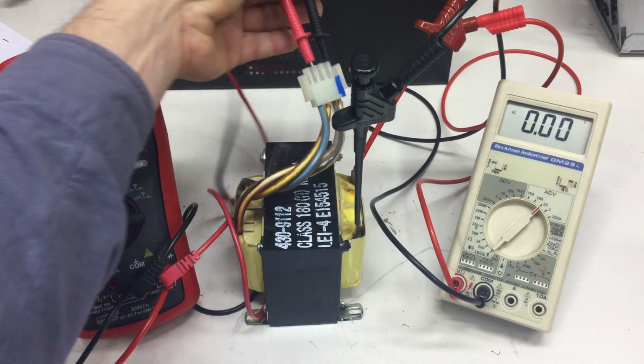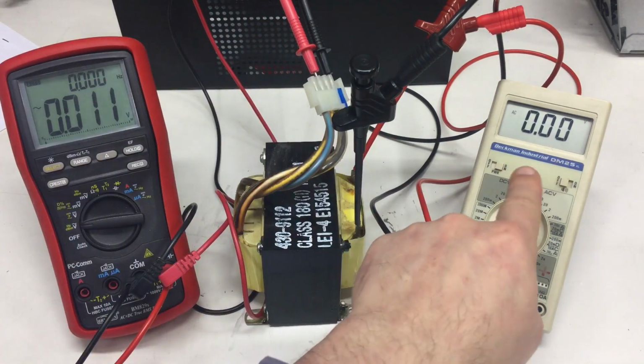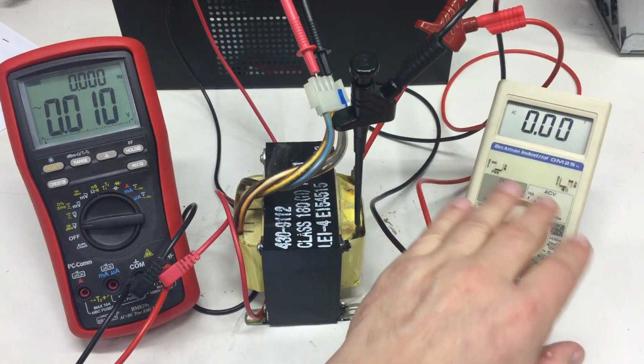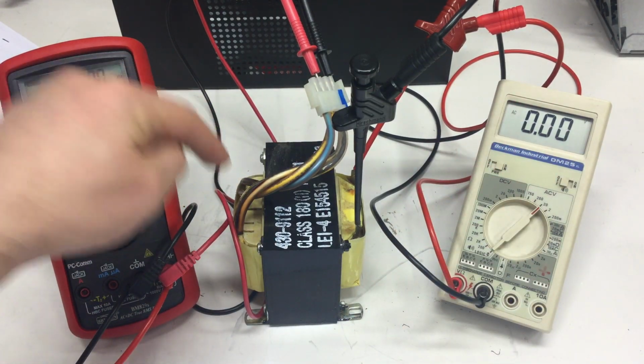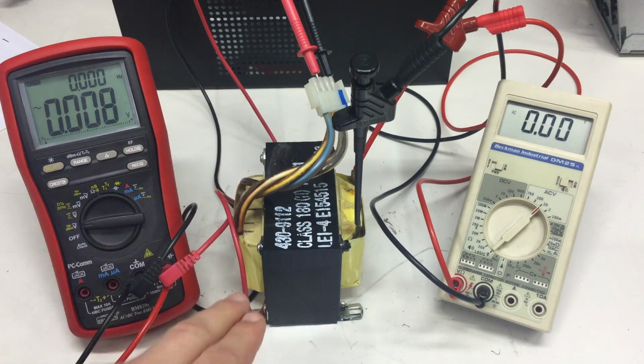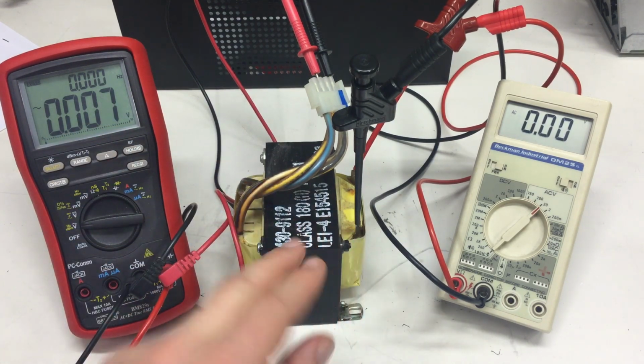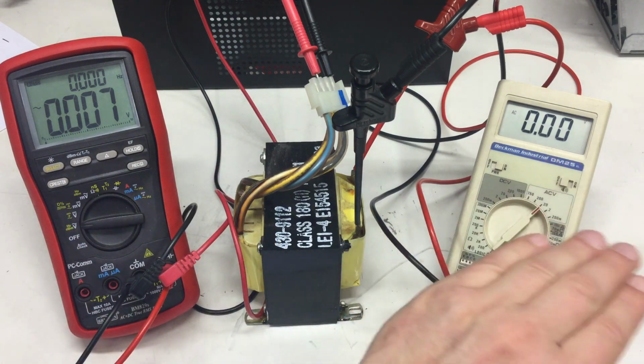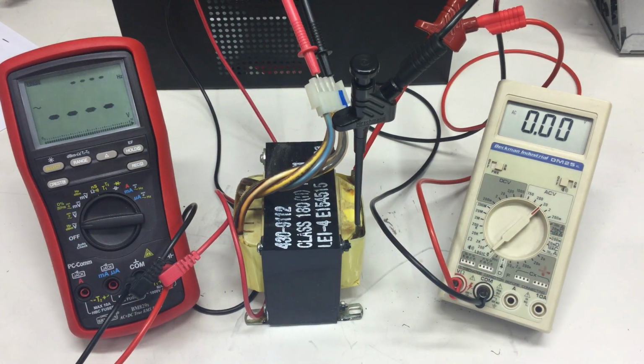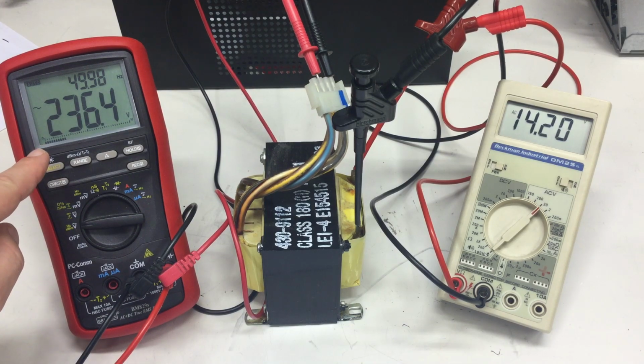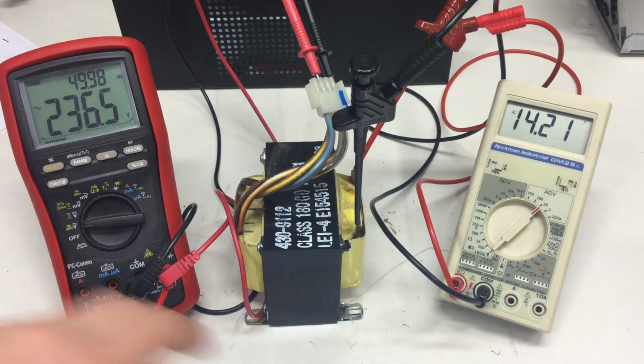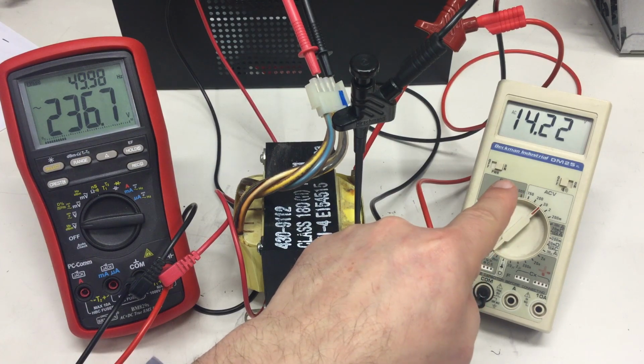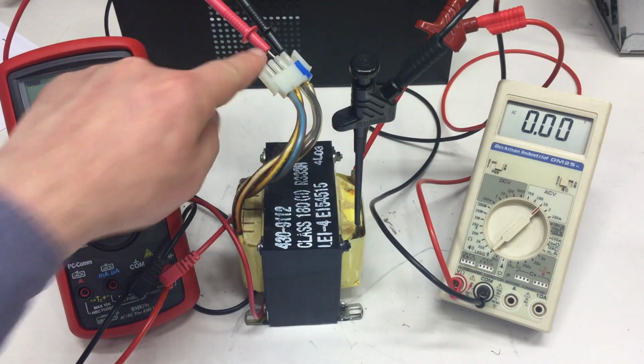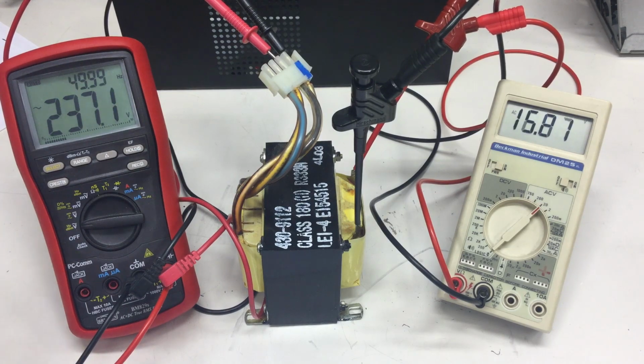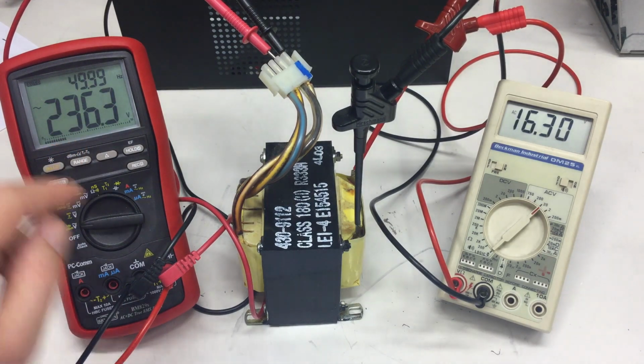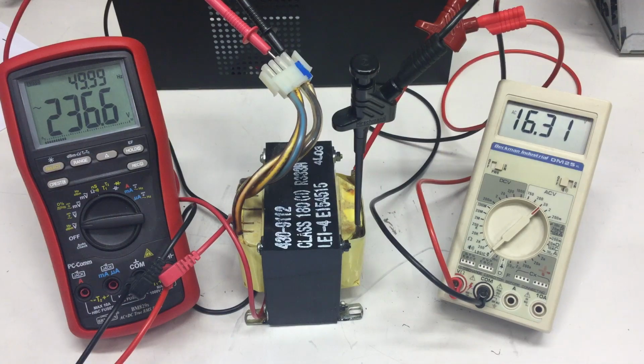Middle tap now, and I expect that voltage to be higher because, yeah, less windings on the primary, so the ratio between primary and secondary gets smaller, so higher voltage here. Let's see. Mains we have still 236 something, and output is now 14.2. And finally, the lowest tap. We are still 236 and 16.3.